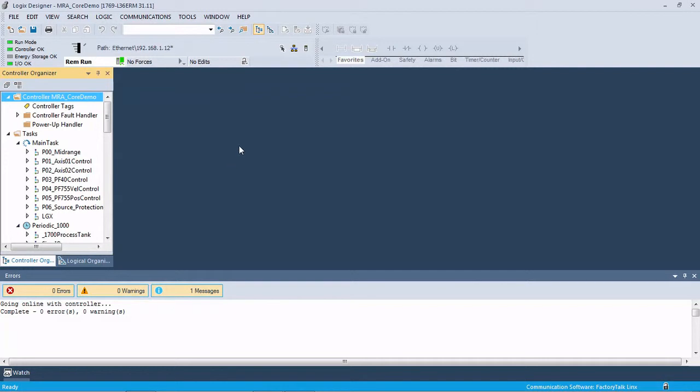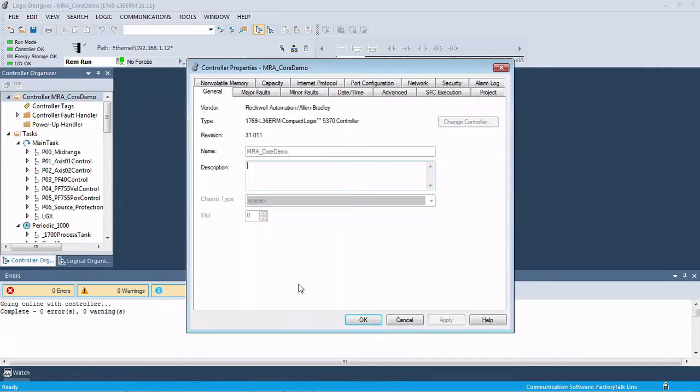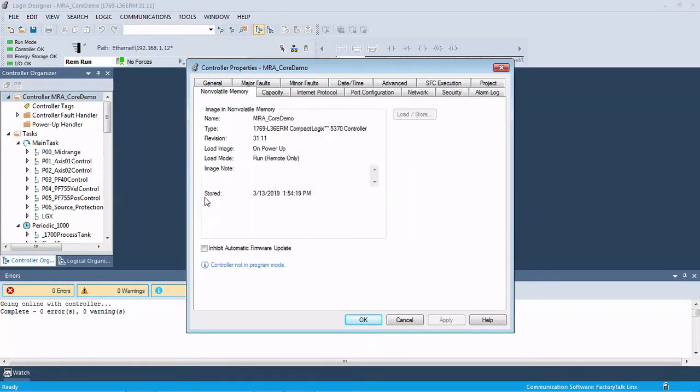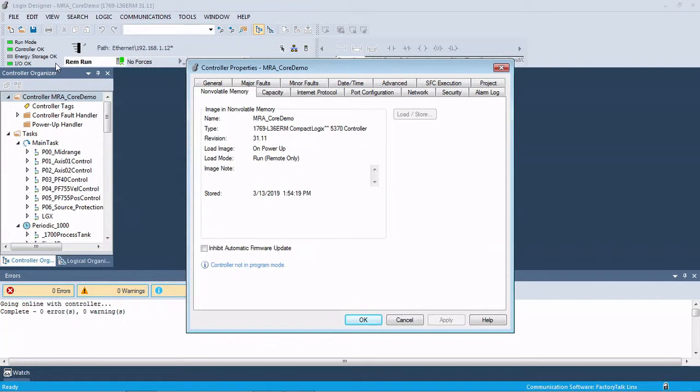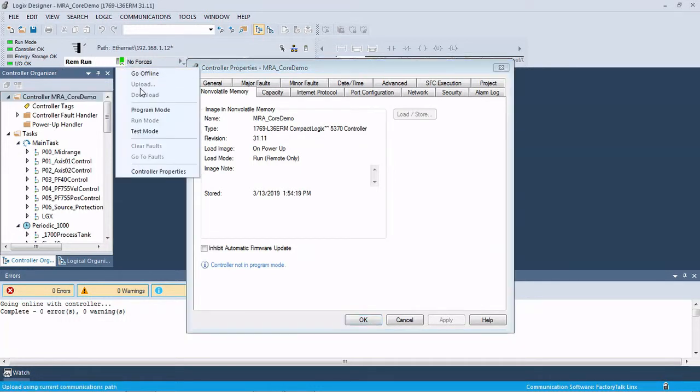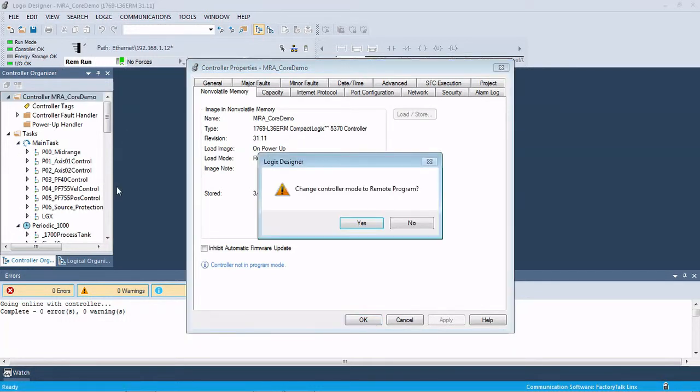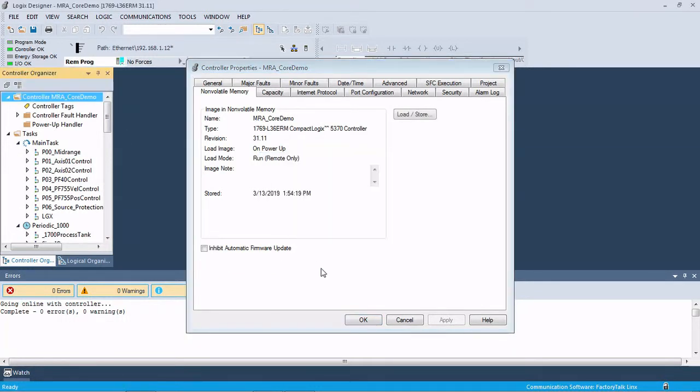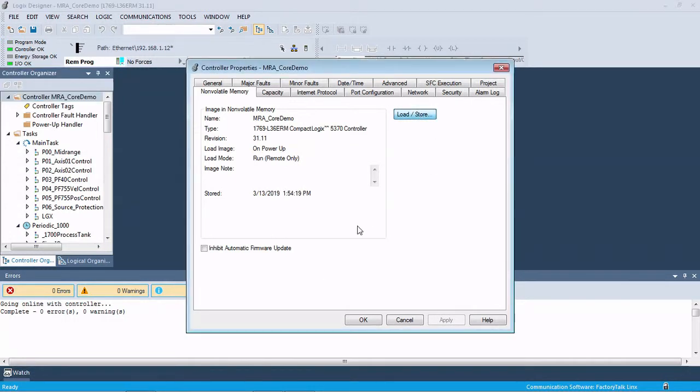So the prep work is you come online with Logix 5000, Studio 5000. You go to Controller Properties and Non-Volatile Memory. You can see here this Load Store button has been grayed out, and that's because we are currently in Run Mode. So what we're going to do is come over and take our processor to program, and then the button comes available. So we're going to click on that.